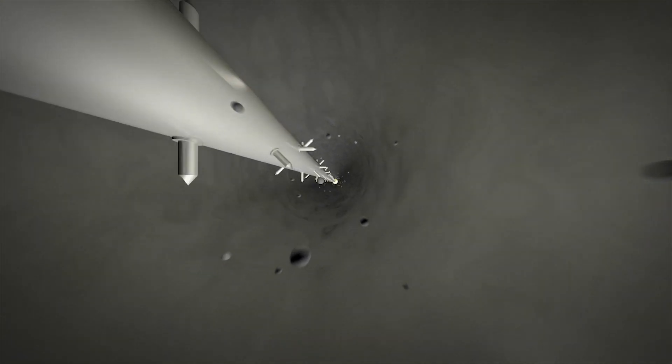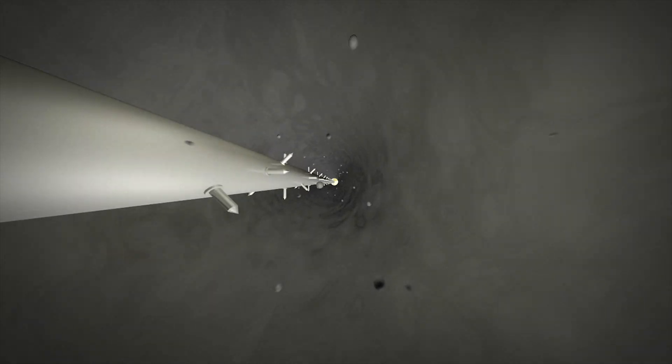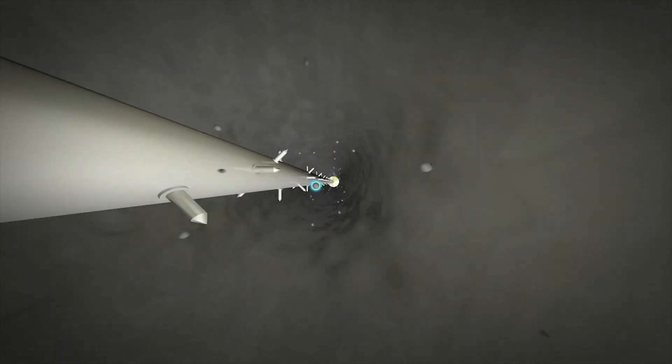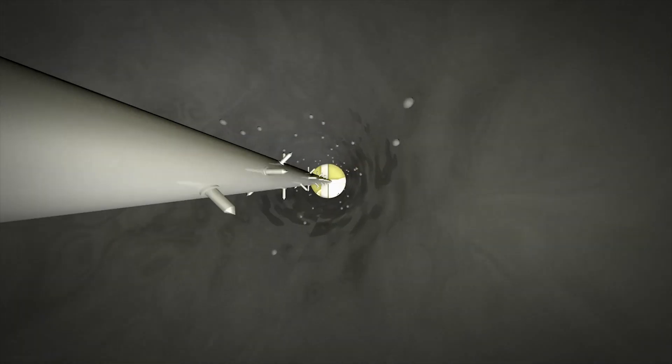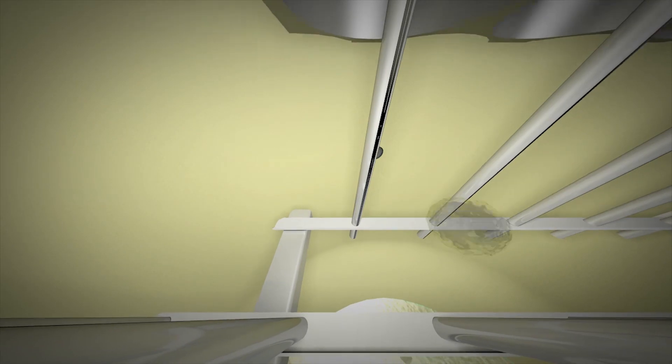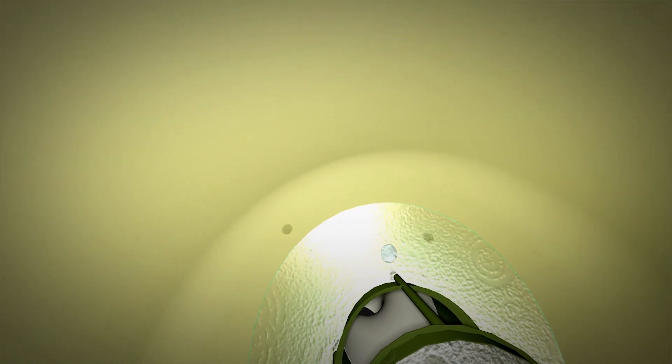they are charged and forced to migrate through the strong electric field towards the collecting area on the tube surface, where they are caught in the process liquid preventing re-entrainment. This liquid collects and is removed whilst the gas goes through to the next stage of the process.